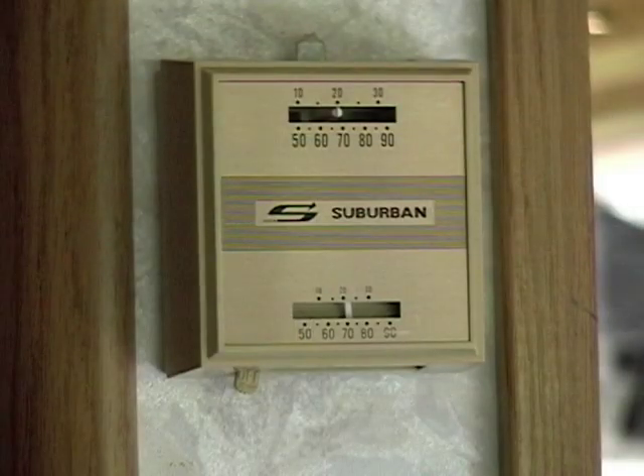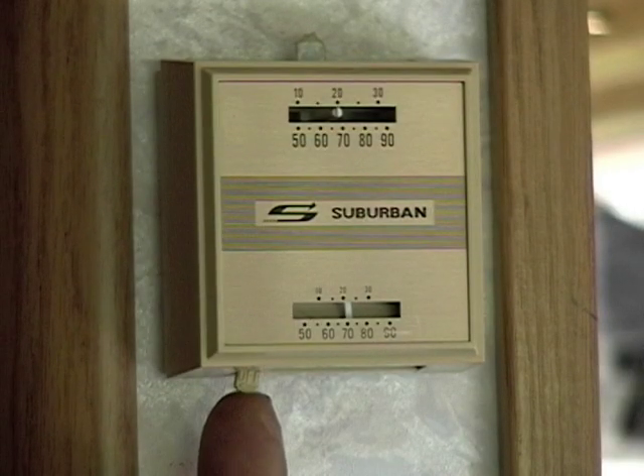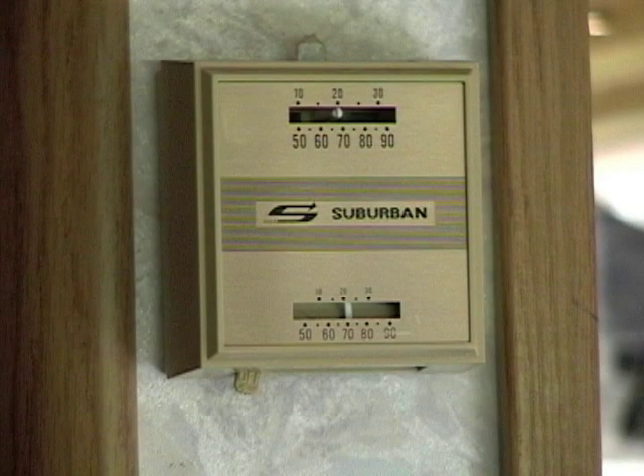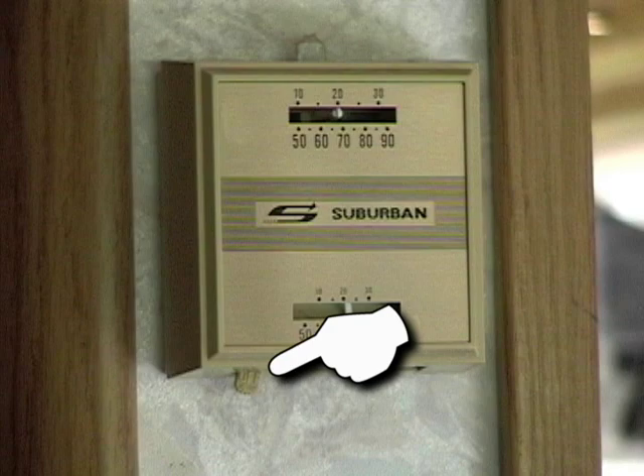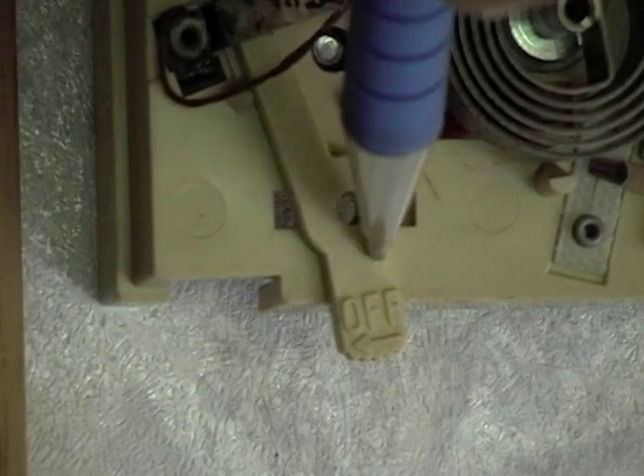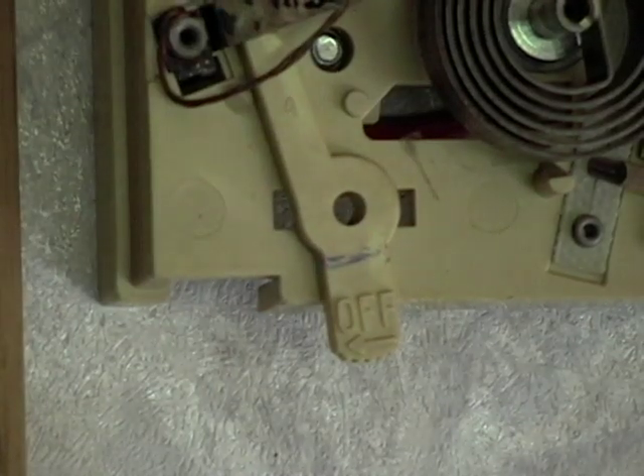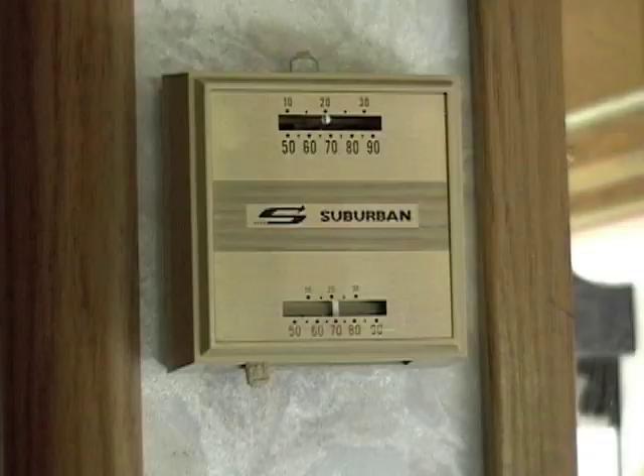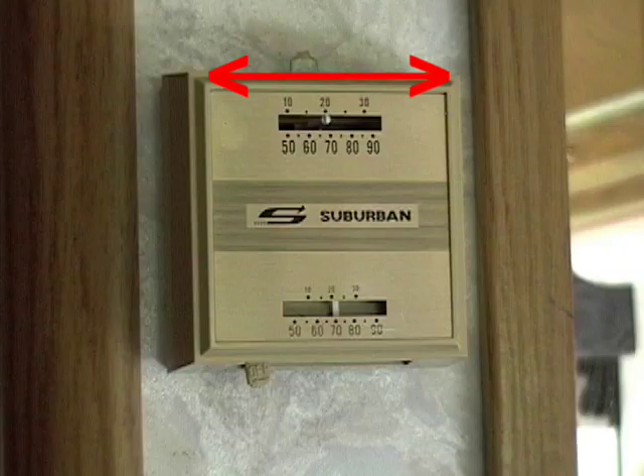If it does nothing, make sure the thermostat is on and set properly. Something I see quite often on these less complicated thermostats, like this one, people forget to flip the on-off switch. Oh, by the way, make sure it has one. Sometimes they get broken off and are stuck in the off position. If the switch is okay, try moving the temperature lever back and forth a few times. The contacts can get dirty and sometimes this helps. If it still won't work, we need to check the power supply.